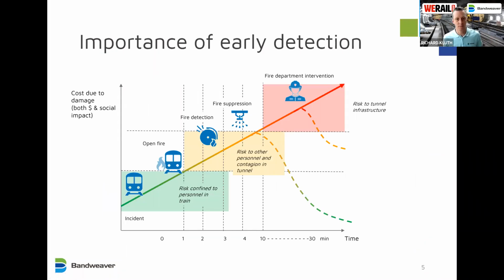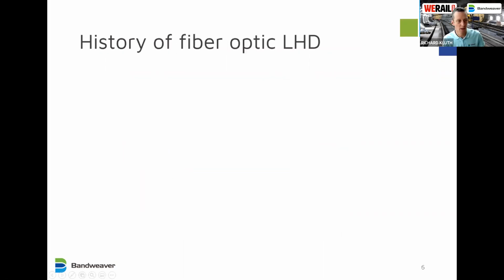So this diagram highlights the build-up of a fire in a tunnel environment, typically starting on the bottom left, where fires start quite small. If you can catch it early on, it can be quite easy to extinguish the fire. But in the latter stages, once the fire really takes hold, temperatures can be in excess of 1000 degrees C. And in this case, there's little you can do to control the fire, and damage to infrastructure can be extremely extensive. It's therefore critical to detect the fire as early as possible.